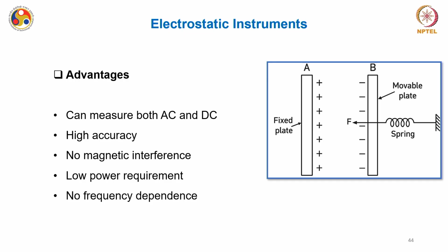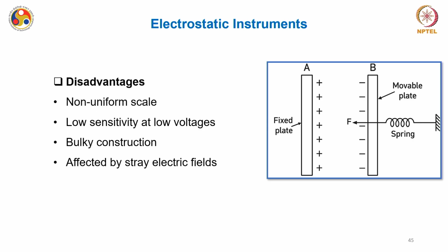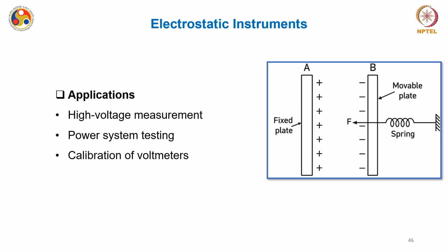The advantage of these instruments is that they can be used for measurement of both kinds of voltage: you can use them for AC voltage measurement and for DC voltage measurement. They have high accuracy, magnetic interference is nil. The power requirement is not very high in this instrument, and the frequency dependency is minimum or nil. The disadvantage is that they have a non-linear or non-uniform scale. Some of the categories have low sensitivity at low voltages, and the construction is a little bulky. They are also affected by stray electric fields, because this is a capacitive device. They can be used for high voltage measurements as well as for low voltage measurements, but usually they are preferred at medium and high voltages. They are useful for power system testing and the calibration of voltmeters.